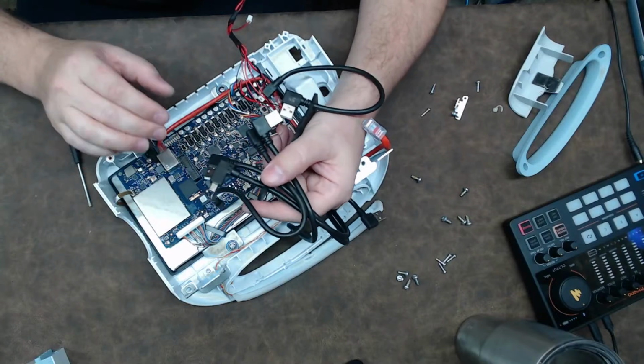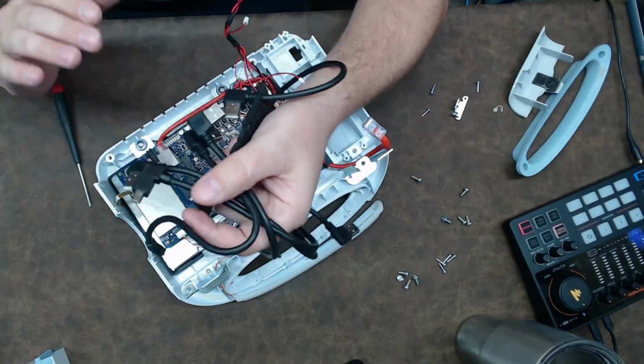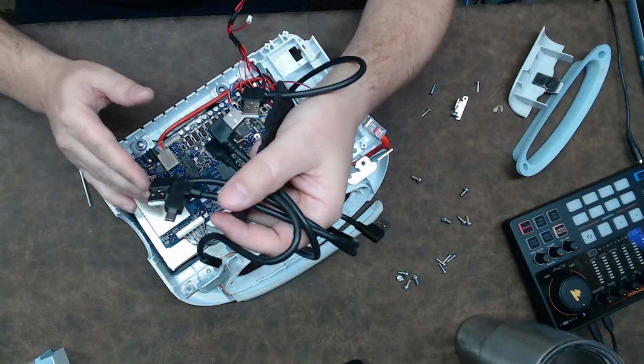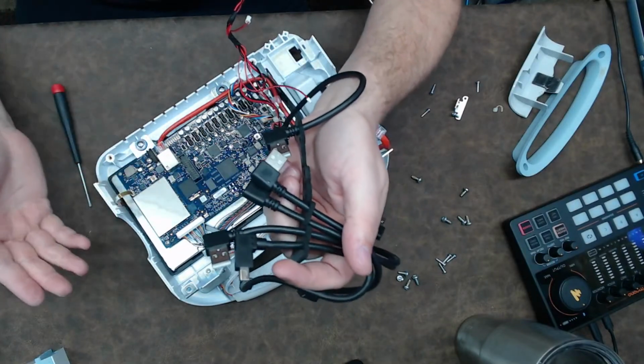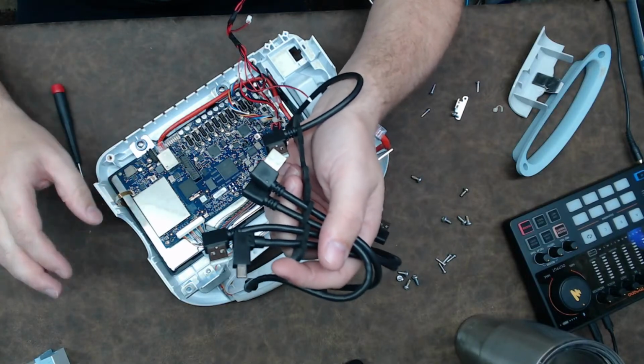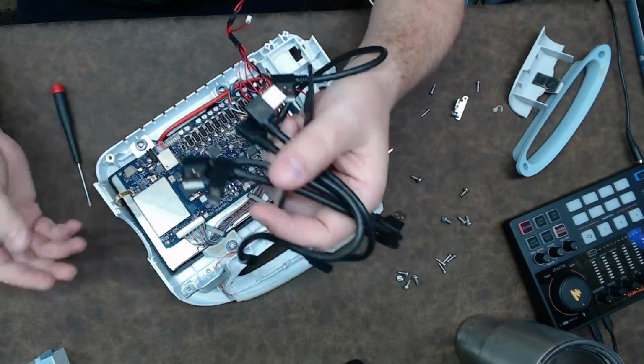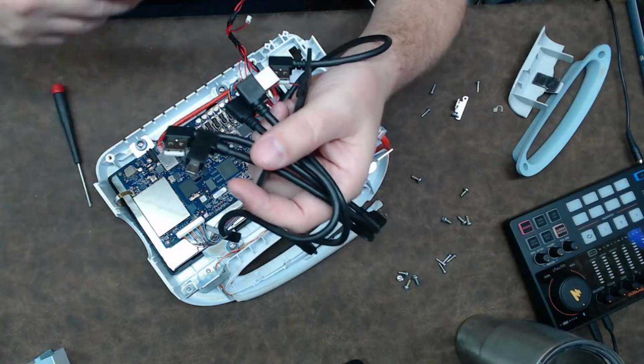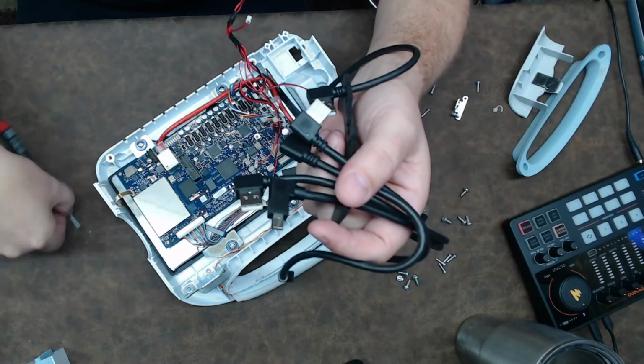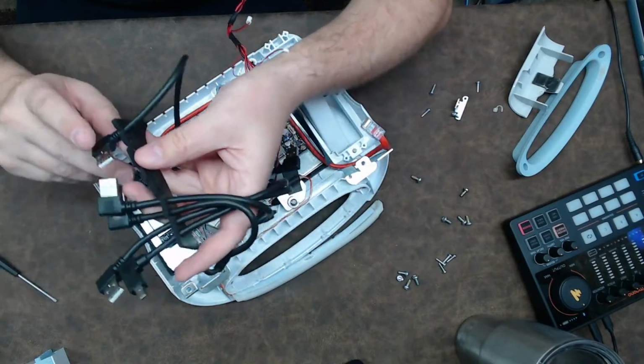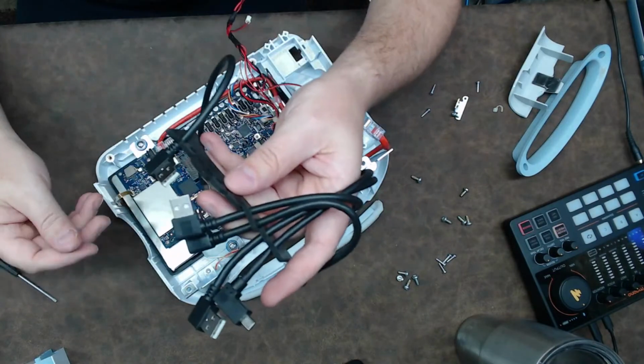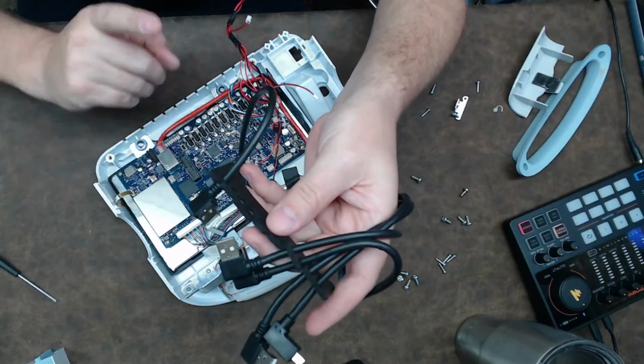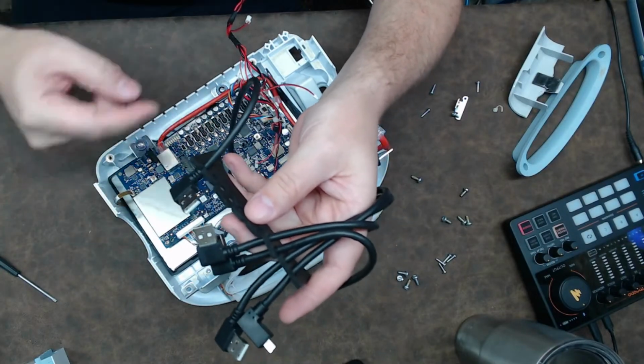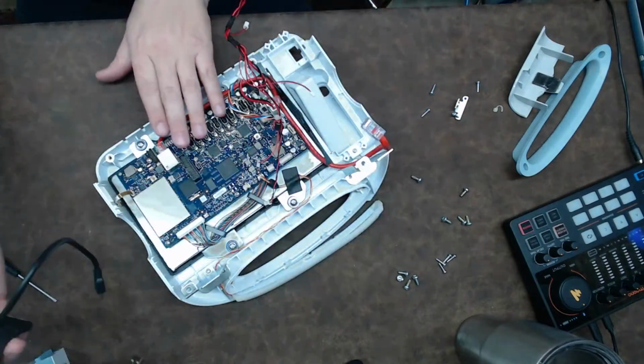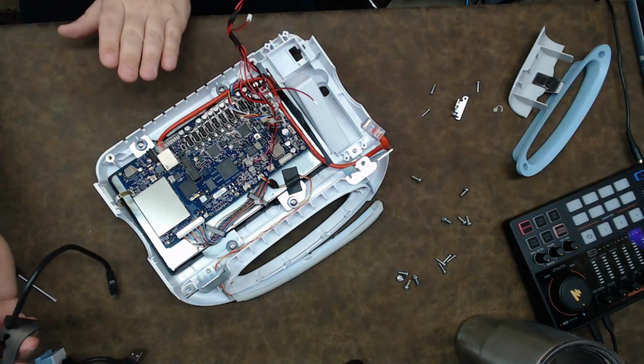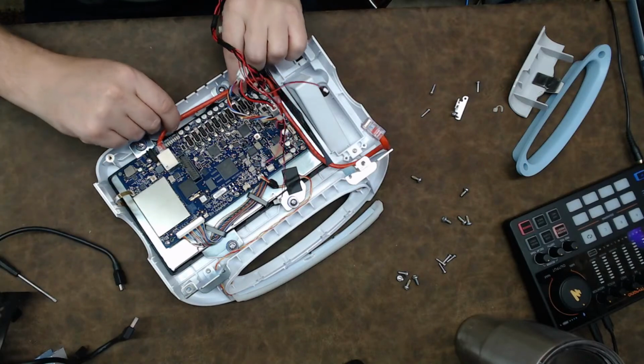So with older medical devices, you always try to plug the USB back into the exact same port it came from, because often with the software, even if you can change the port options, it's usually locked down and only the OEM can change stuff like that. That's pretty common in things like older ultrasounds and whatnot. Just be mindful, guys, if you ever disconnect USBs from a medical device, always try to plug it back into the same port. That way, whatever the baud rate for that port is set up as, you're not messing with it, okay? Some of you guys are like, what's a baud rate?